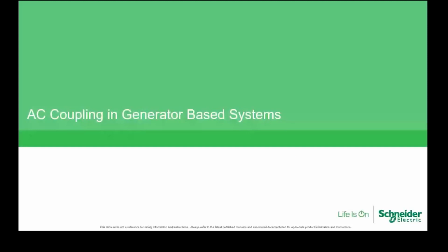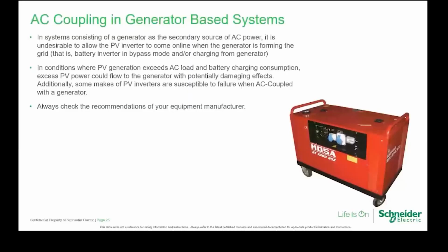AC coupling with generator-based systems. Basically, over here, we have an AC coupled system, which, instead of having the grid, has a generator. And that becomes your secondary source of AC power. The main thing is you've got to make sure that the grid-tied inverter does not see the generator, or the generator does not see the PV inverter, whichever way you want to look at it. So you either have a bypass mode, or you actually have a switch over, so that interconnects, so that not both of them are on at the same time.